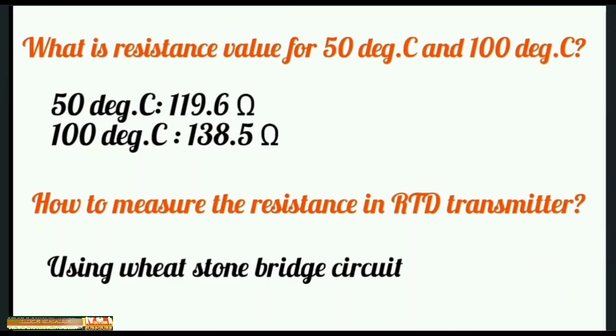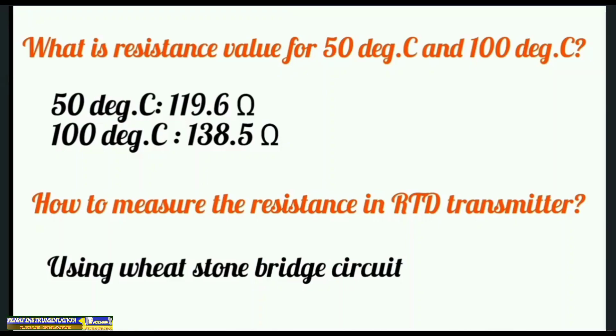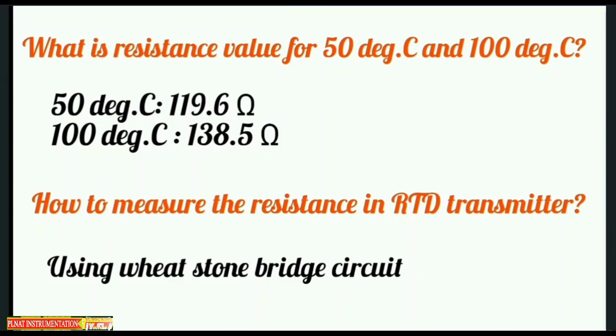What is the resistance value at 50 degrees Celsius and 100 degrees Celsius? At 50°C: 119.6 ohms. At 100°C: 138.5 ohms. How to measure the resistance in an RTD transmitter using a Wheatstone bridge circuit?